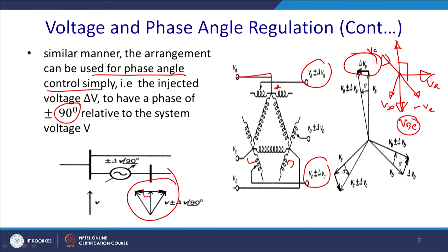For relatively small angle adjustment, the resultant angular change is approximately proportional, since delta and sin delta are almost the same. Then the angular change is proportional to the injected voltage, while the voltage magnitude remains almost constant. So, this value will change. For large angle adjustment, the voltage will change. The magnitude of the system voltage will appreciably increase or decrease.